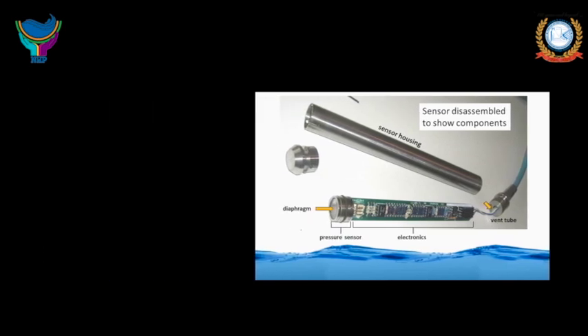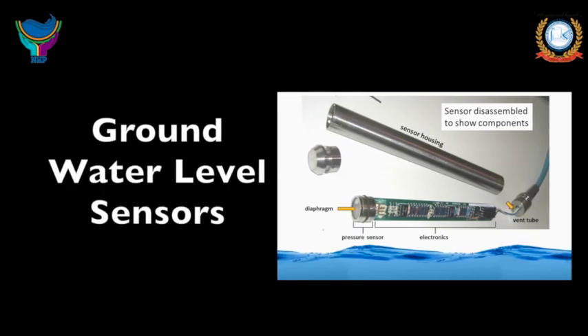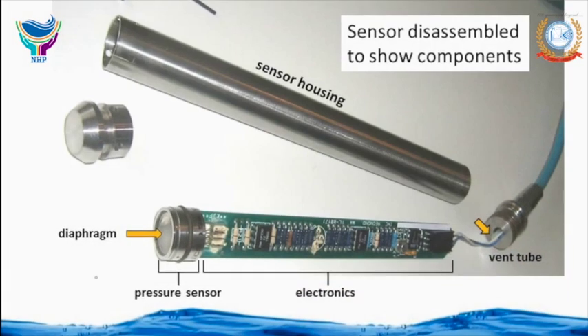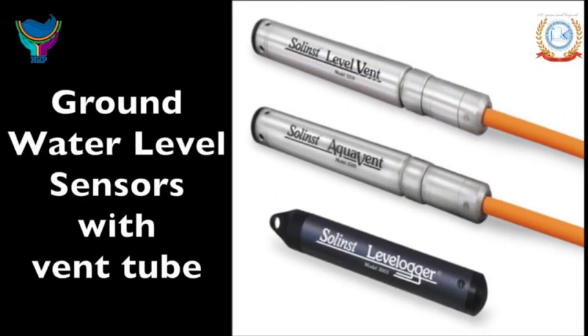The groundwater level sensors. A hydrostatic level probe typically uses a pressure sensor to measure the water level. The main component of a pressure sensor is the sensing diaphragm, which converts the difference in pressure between either side of the diaphragm into a measured signal. The front of the diaphragm measures the water level pressure, hydrostatic pressure, plus the barometric air pressure pushing down on the water.